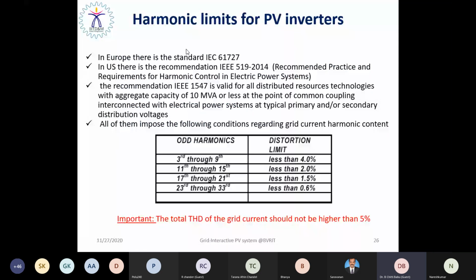So whatever control technique you impose on this voltage source inverter, it has to satisfy the international standards while integrating the solar PV system with the utility grid, because the harmonic limits are very important. Non-sinusoidal current will not be injected at any cost. There will always be lower order harmonics, so those have to be rejected in the inverter output itself. We follow two standards internationally, a US standard and a European standard called the IEC 61000 series.